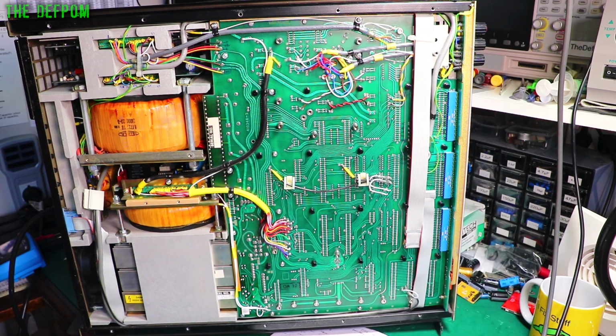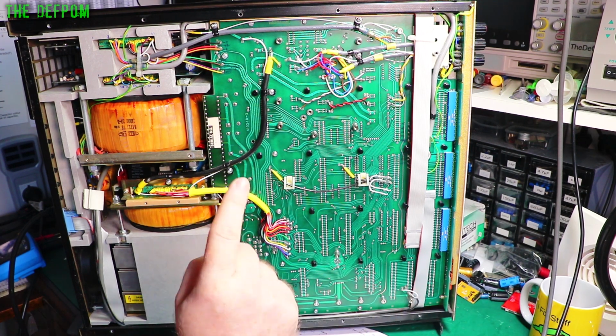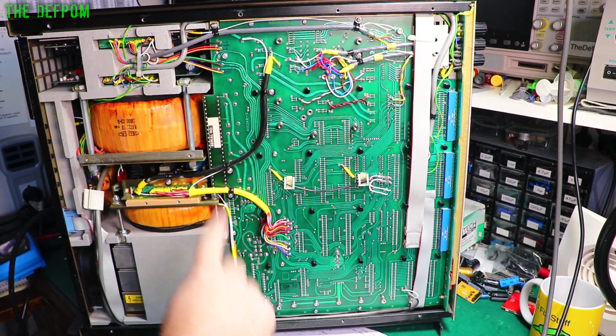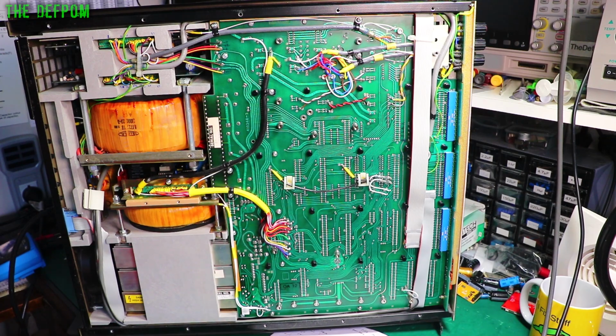If you're paying attention as well, you might notice there's a little adjustment just down here, all by itself, which is a bit weird. That's used for the guard adjustment. There's 2 adjustments, one on the power supply and one down here, and you use those 2 adjustments and you get the noise on the guard terminal down as low as you can during the calibration. So that's what that's for, in case you care.